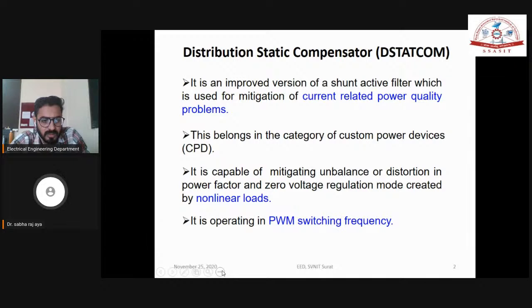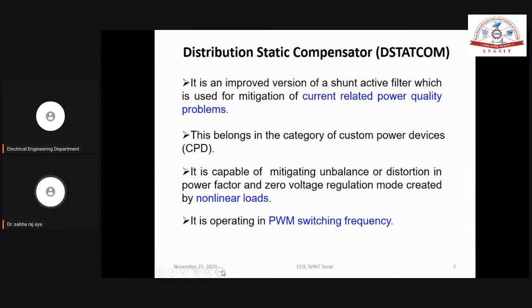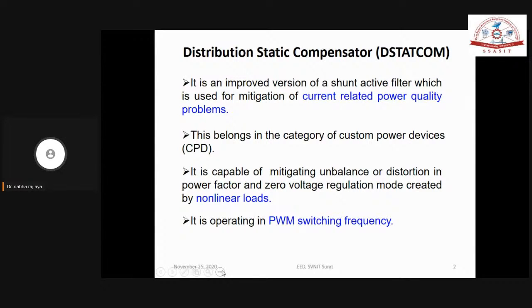Okay. So here the basic application is, generally we have two types of problem. Maybe due to load, you are going to have a problem in the supply system. Second, maybe the supply itself has some problem. If we see a problem due to load, it means the load is demanding current, and whatever problems are there in that demanded current, we want to solve them. For that you can use this distribution static compensator. Means by using the distribution static compensator, we want to eliminate current based power quality problems. Simply you can say like this.